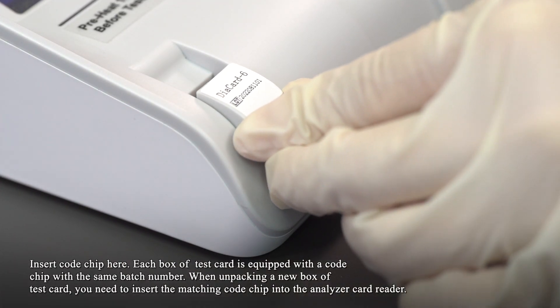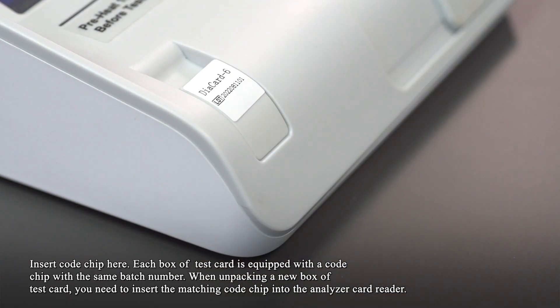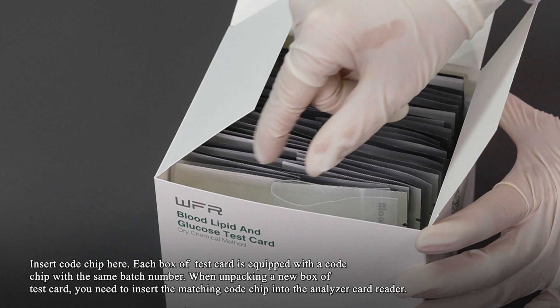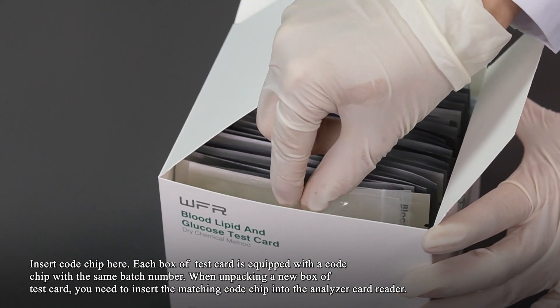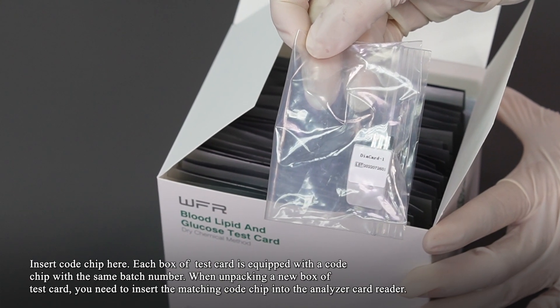Insert the code chip here. Each box of test cards is equipped with a code chip with the same batch number. Remember, when unpacking a new box of test cards, you need to insert the matching code chip into the analyzer card reader.